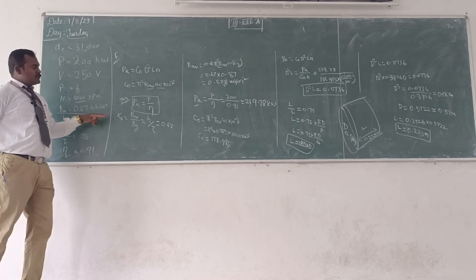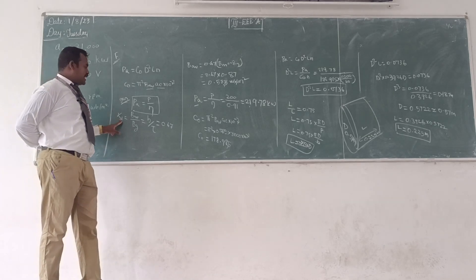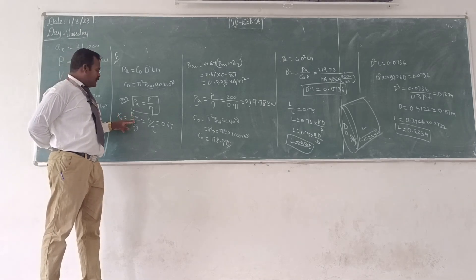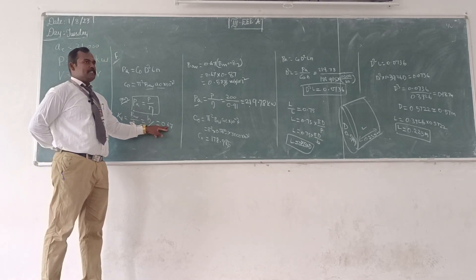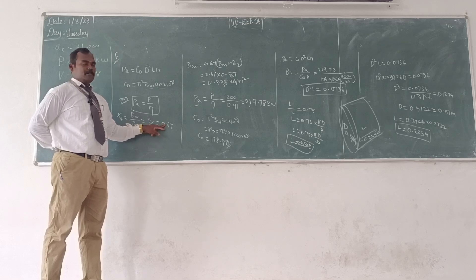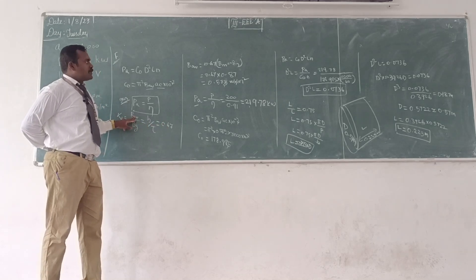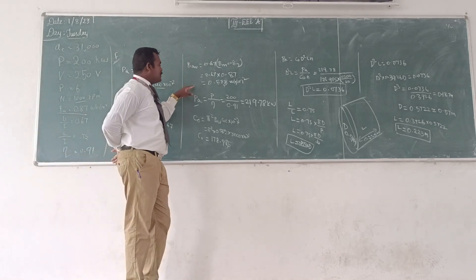We can calculate BAV by using the form factor formula. The form factor Kf should be equal to BAV divided by Bmax, which equals the pole arc to pole pitch ratio of 0.67. From that we can calculate the BAV value.